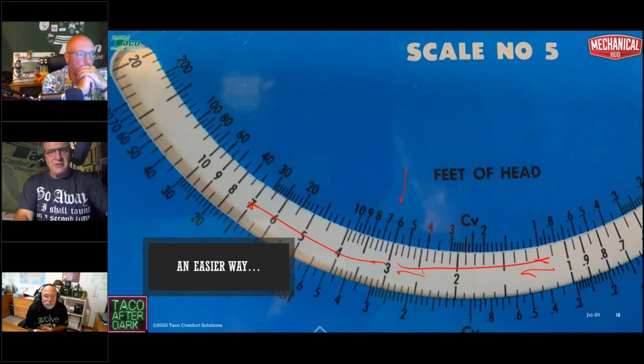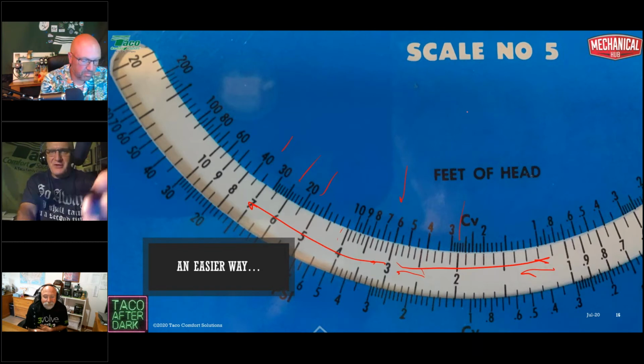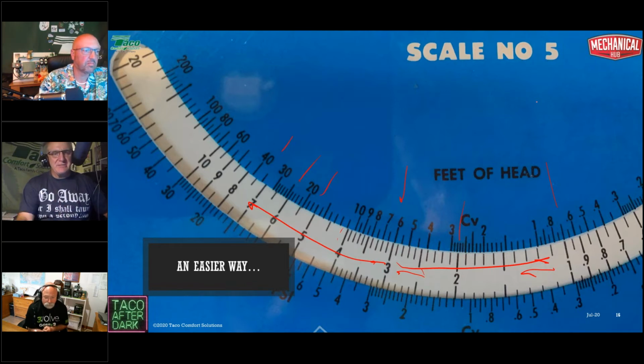So again, I can look at this. At 3 gallons a minute, it's 6 foot of head. At 4 gallons a minute, it's 11. At 5, it's 17. At 6, it's 24. At 7, it's 33. At 2 gallons a minute, I'm at 2 3/4. At 1 gallon a minute, I'm at 0.7. Okay, so those are the points on my system curve.